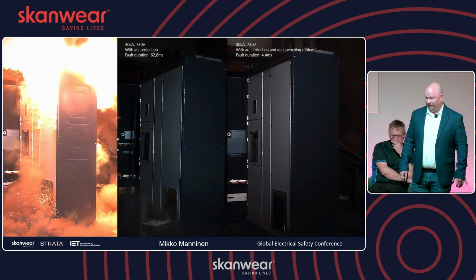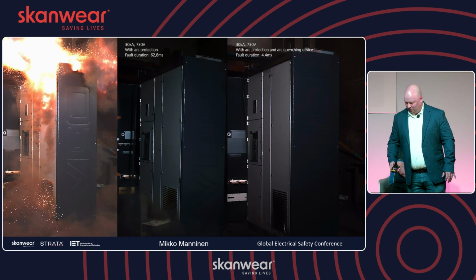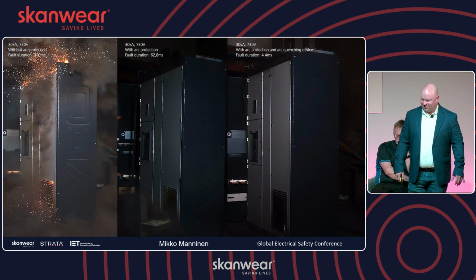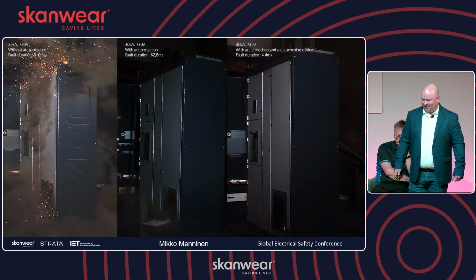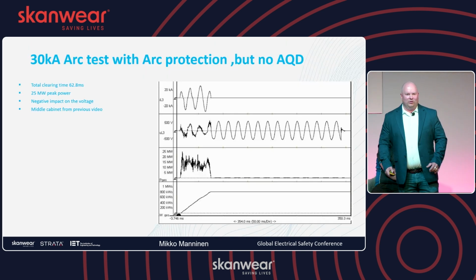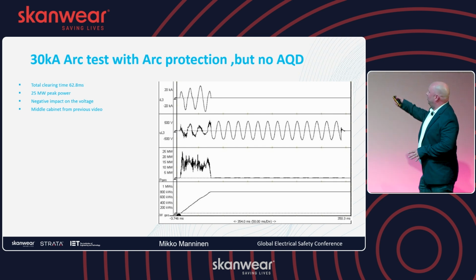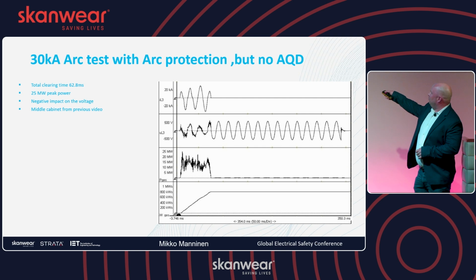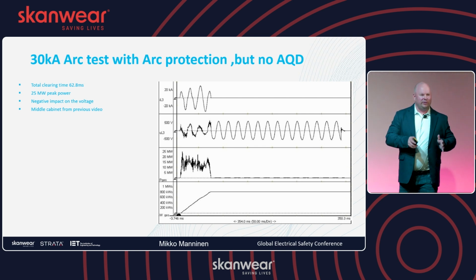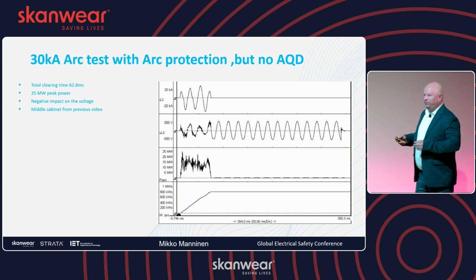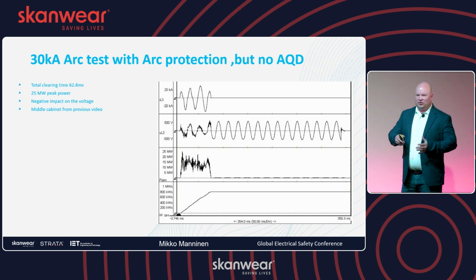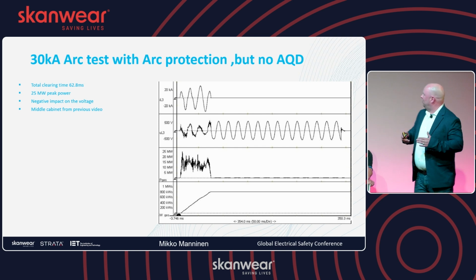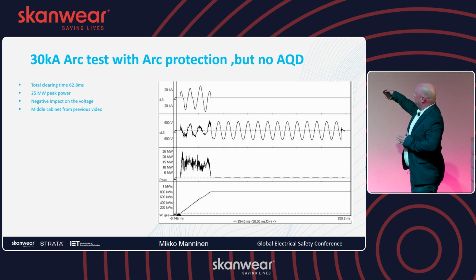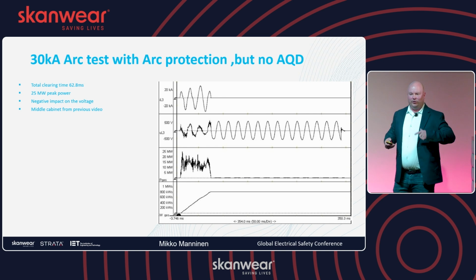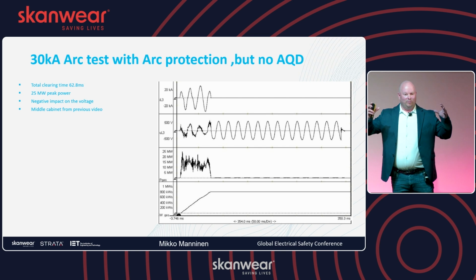So it keeps burning until the copper is gone and vaporized. So I will skip to the next one to save a little bit of time. It did. So this is how it looks. This is 30 kiloamps now. Have a look at this second from the bottom. This is how the arc flash looks from the transformer point of view. It's a lot of distortion. When you burn copper, when you burn the electrode, the impedance of the fault is changing all the time. So arc flash looks like this. This is 30 kiloamps until you have the third cycle full and the circuit breaker is completely open.